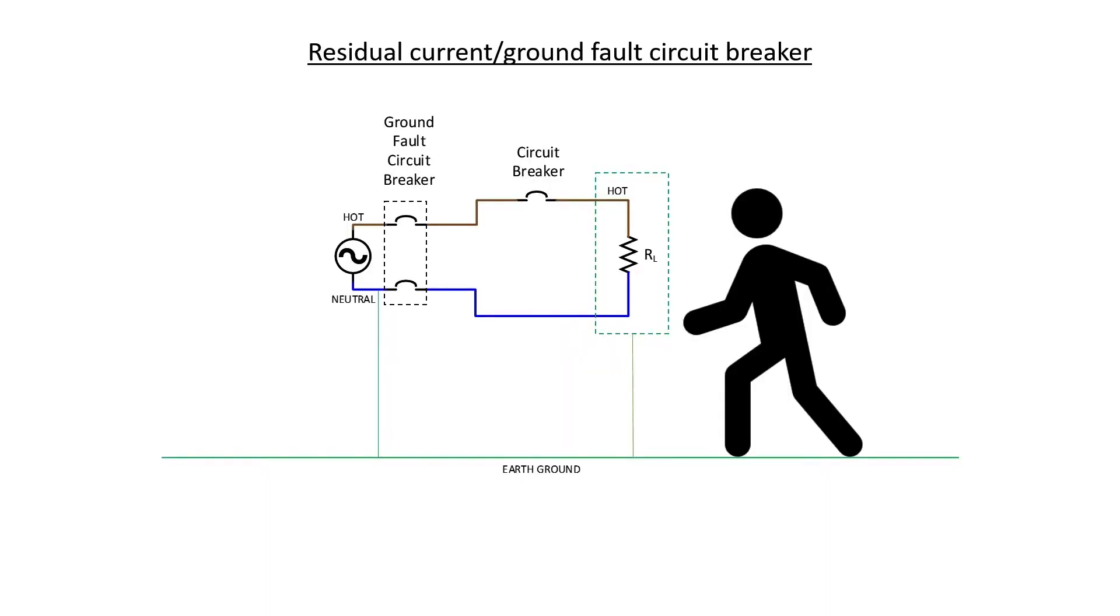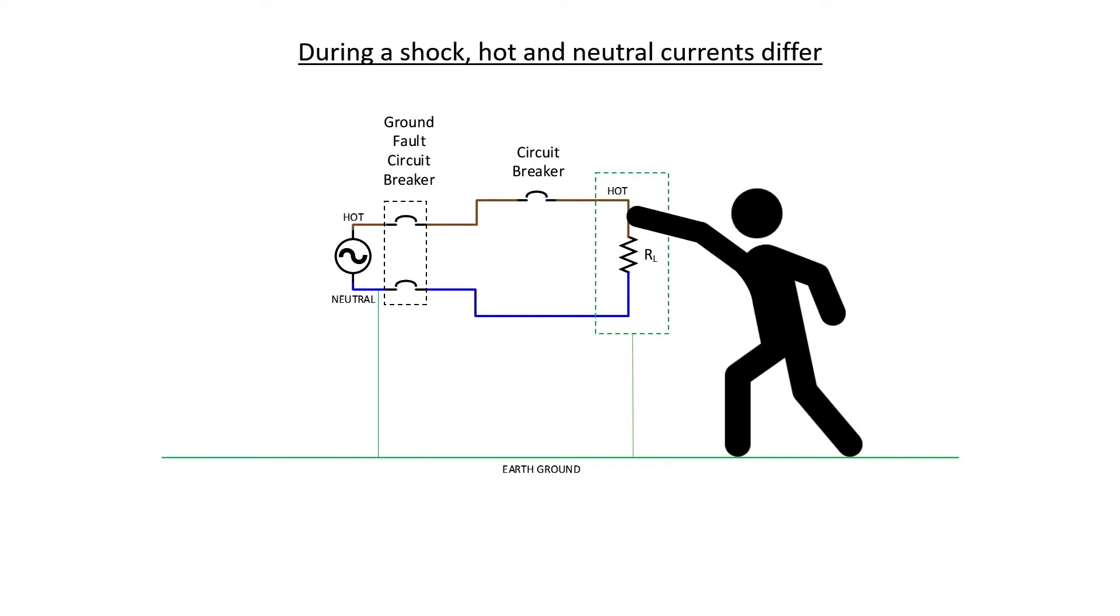Let's see how it would work in the case of a shock. Let's again assume that somehow a person comes along and manages to avoid a grounded case and make contact with the hot side of this circuit by accident. Initially, we have equal amounts of current going out through the hot and back through the neutral. But when the person makes contact with the hot, then we're going to have unequal amounts of current going out through the hot and coming back through the neutral. That will cause the ground fault circuit breaker to trip.